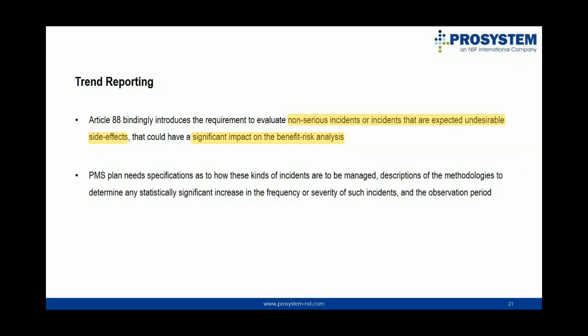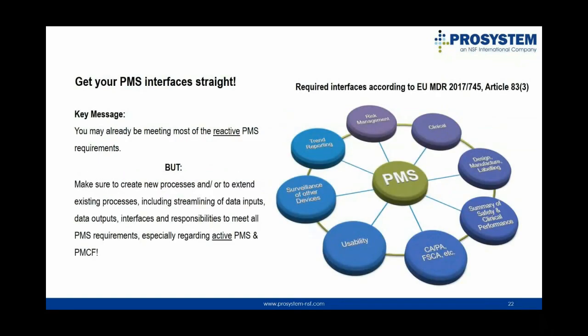So the PMS plan needs to specify how these kinds of incidents are to be managed. The PMS plan also needs descriptions of the methodologies to determine any statistically significant increase in the frequency or severity of such incidents, and obviously the observation period. If there are trend reporting procedures in place that meet the detailed requirements of the MDR, it may be sufficient to reference them in the plan. So in conclusion, the key messages would be that one of the major issues will be to tackle the currently available procedures to contribute to the PMS and PMCF, to identify the missing interfaces, and to make sure that these interfaces share the required data inputs and outputs.